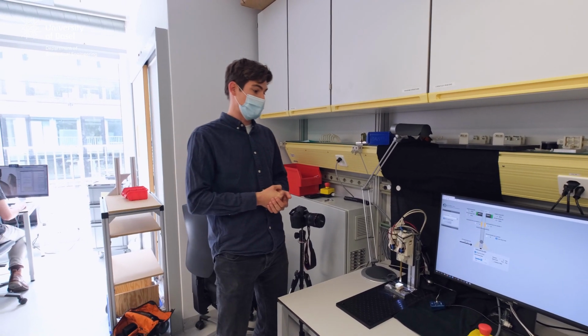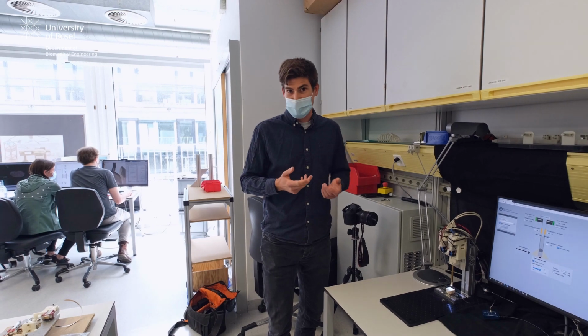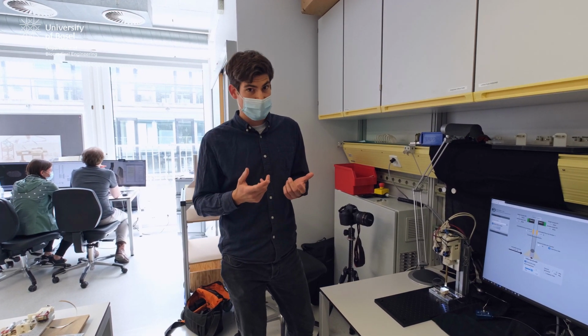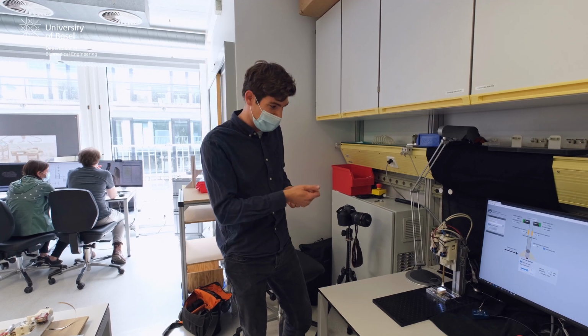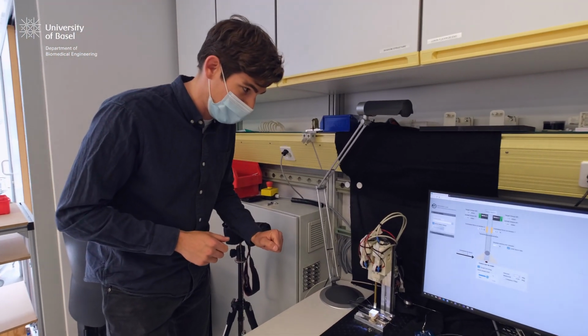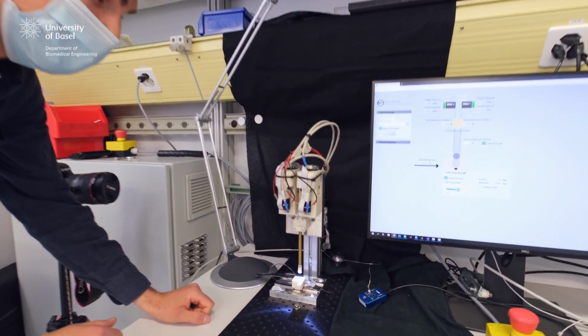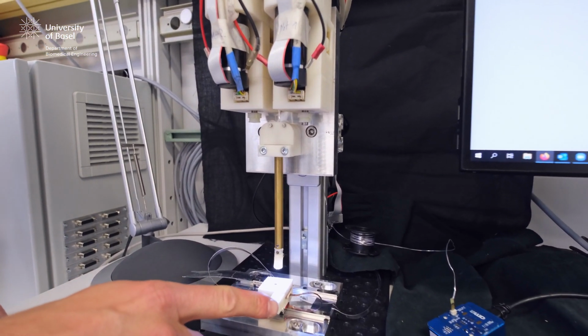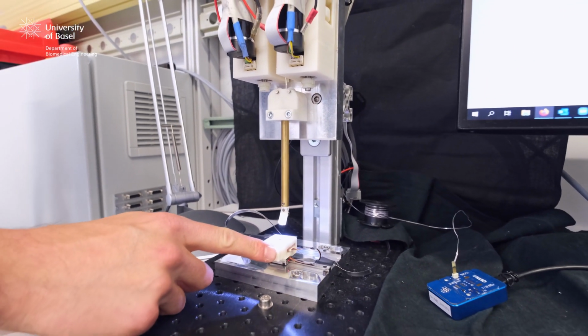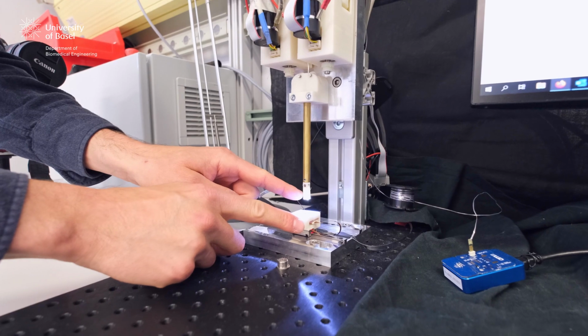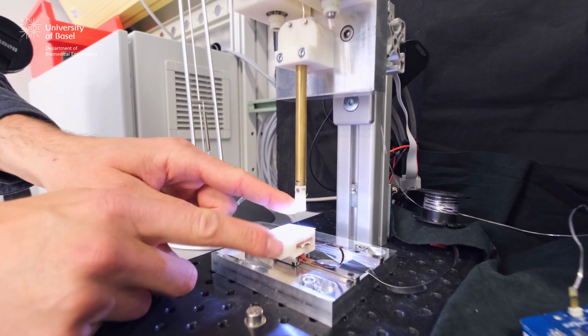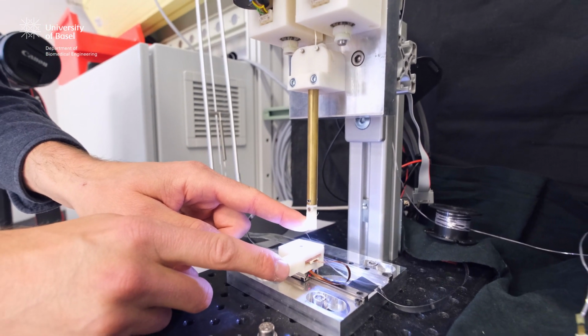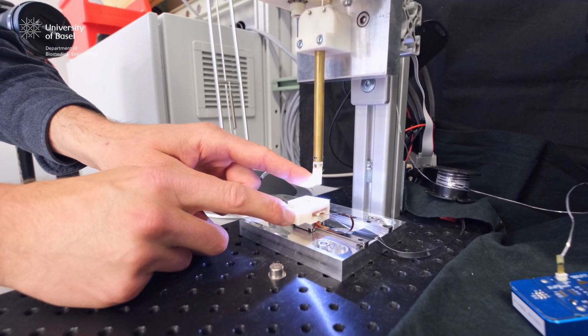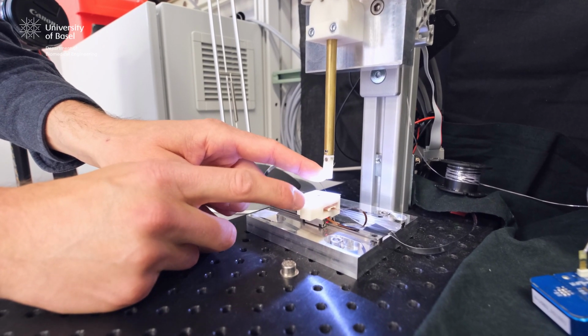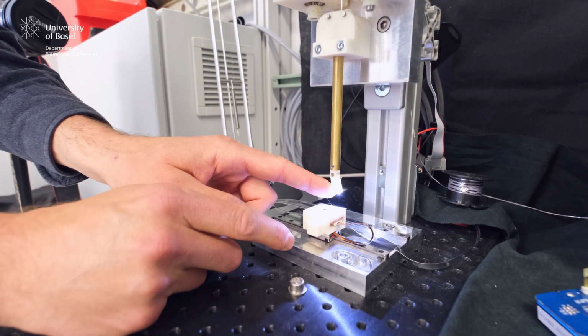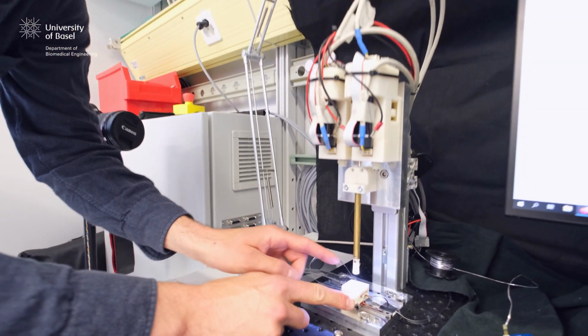Another good thing is that you can measure the deflection of these springs, which gives you an idea of the torque at the endoscope joint. I can show you what that can be used for. For example, if the endoscope is moving and touches some tissue, it doesn't necessarily move to keep this point of view in focus, but instead we can limit the torque applied to the endoscope joint, which makes it safer.